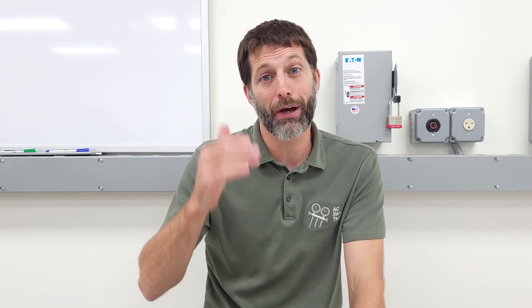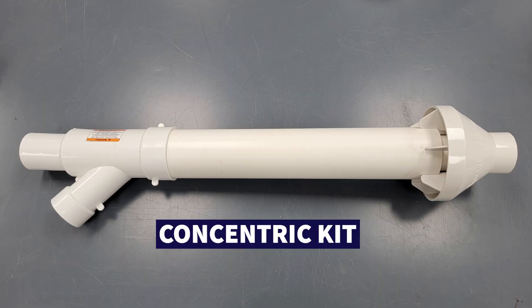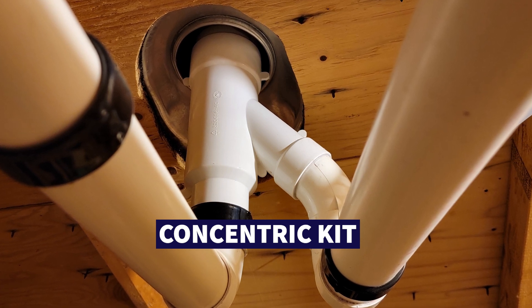That's what's occurring if you have the gas furnace in your basement or within the building structure. If it's in the attic, there's going to be an air exchange happening in the attic, but that's not as bad as within the building. I always install that second pipe, and you can still put one hole out of the building with a concentric kit for a nice clean look when you exit the building.